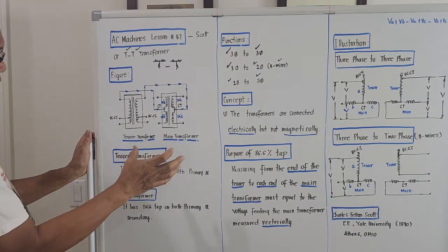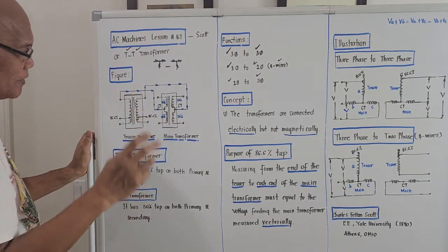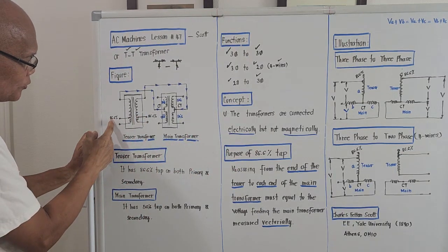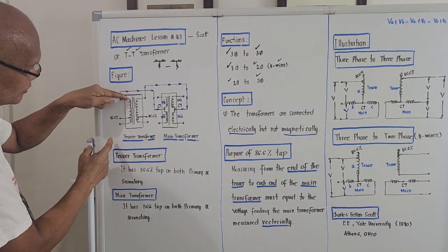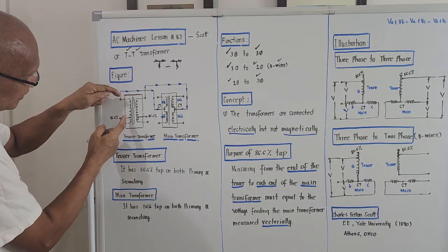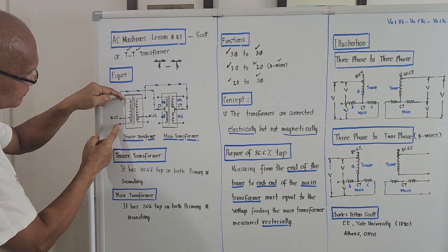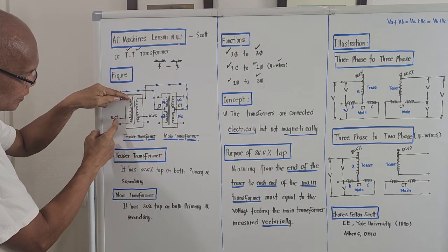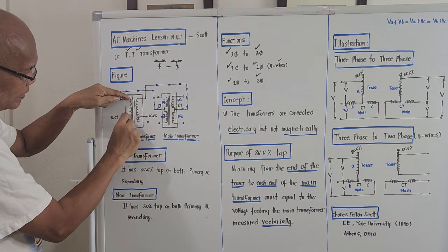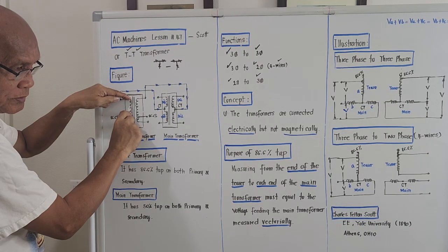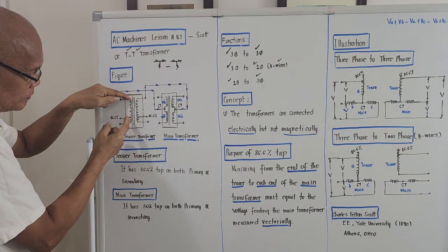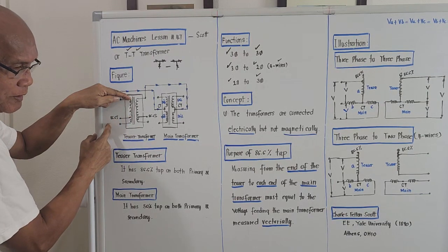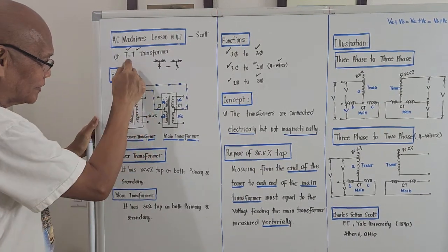For the teaser transformer, there is a tapping, but the tapping is actually a different percentage. It is 86.6%, meaning with respect to this end here, up to here. End to end is 100%. But for it to be a teaser transformer, the tapping is only up to 86.6%, meaning some part of it is not used. So we are bringing out a terminal at the 86.6% tapping for it to fall under a TT transformer.